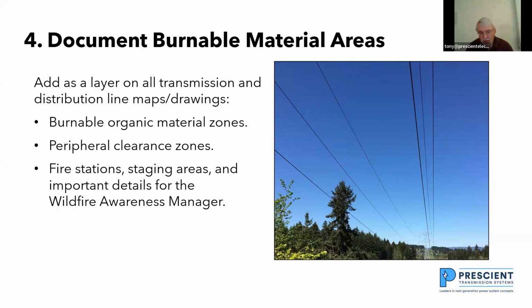So one of the concerns we have is that vegetation management today is focused on trees not contacting the line, and lines not sagging down into trees. When I look at peripheral clearance zones, when I go out and look at the transmission lines in Oregon, for example, in a Tillamook forest, that's a state forest in Oregon, there's a 115 kV line going through the forest. I see trees that are upslope from the transmission line right on the edge of the right of way that are 100 feet tall. If those trees fall down onto a transmission line in a high wind condition, that could ignite a wildfire. And that's something that we want to know about immediately and respond to immediately.